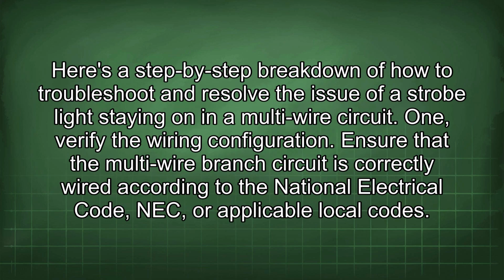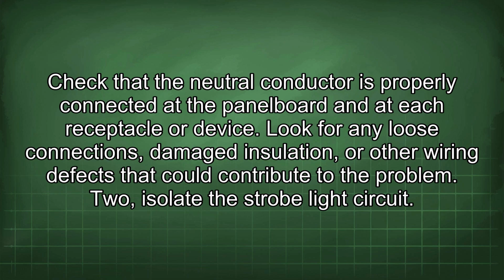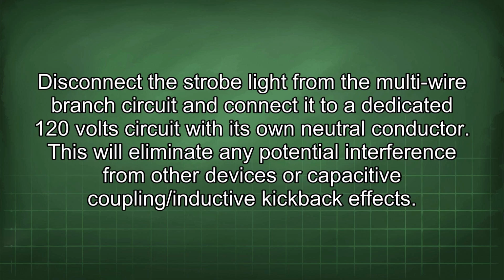Here's a step-by-step breakdown of how to troubleshoot and resolve the issue of a strobe light staying on in a multi-wire circuit. 1. Verify the wiring configuration. Ensure that the multi-wire branch circuit is correctly wired according to the National Electrical Code, NEC, or applicable local codes. Check that the neutral conductor is properly connected to the panel board and at each receptacle or device. Look for any loose connections, damaged insulation, or other wiring defects that could contribute to the problem. 2. Isolate the strobe light circuit. Disconnect the strobe light from the multi-wire branch circuit and connect it to a dedicated 120-volt circuit with its own neutral conductor. This will eliminate any potential interference from other devices or capacitive coupling/inductive kickback effects.